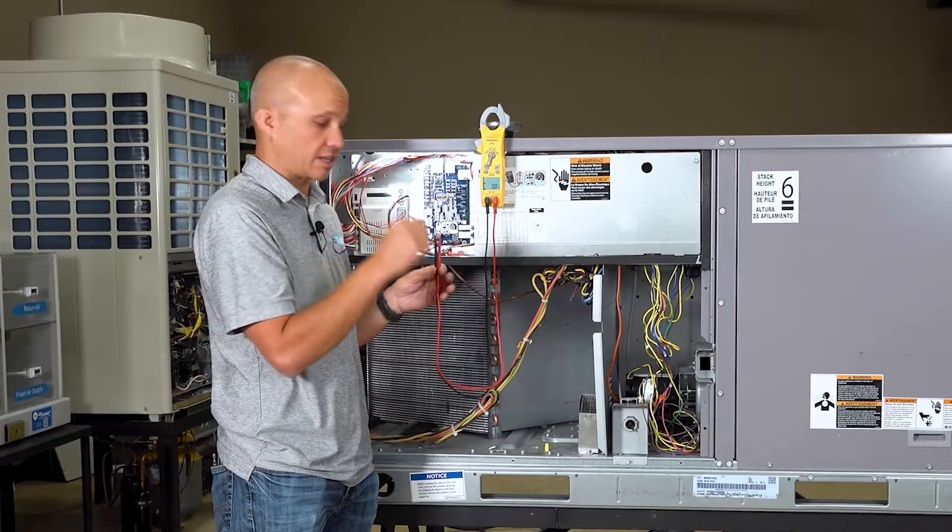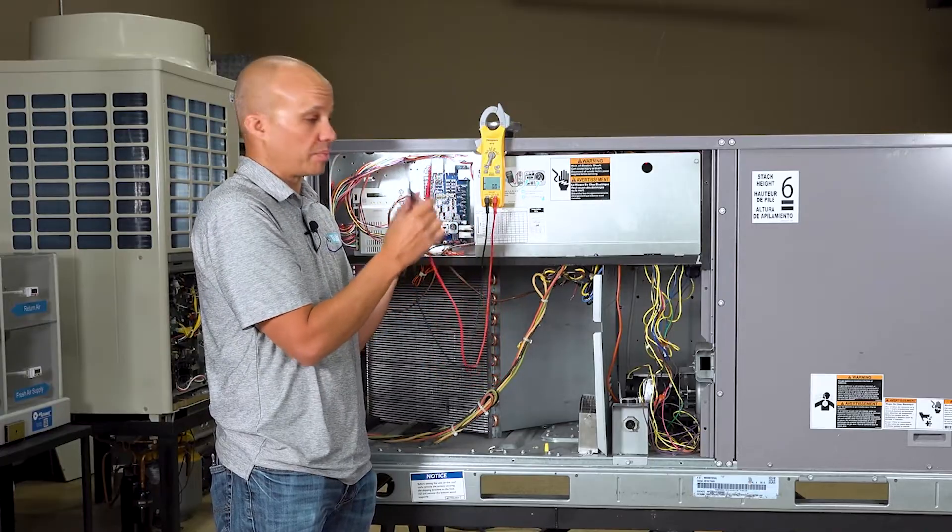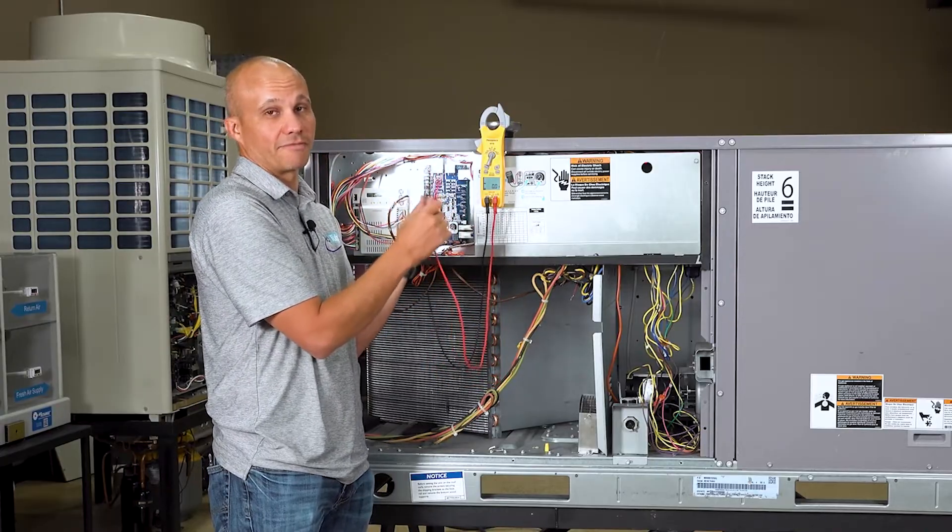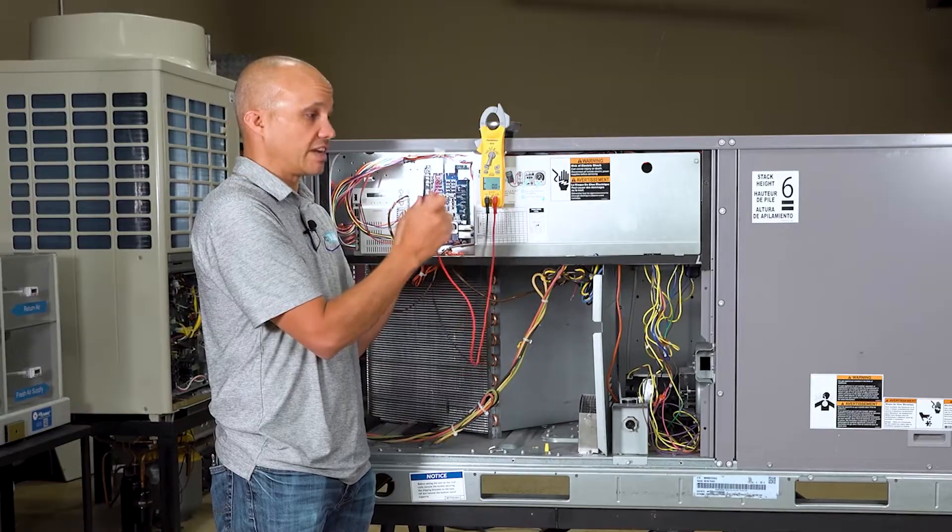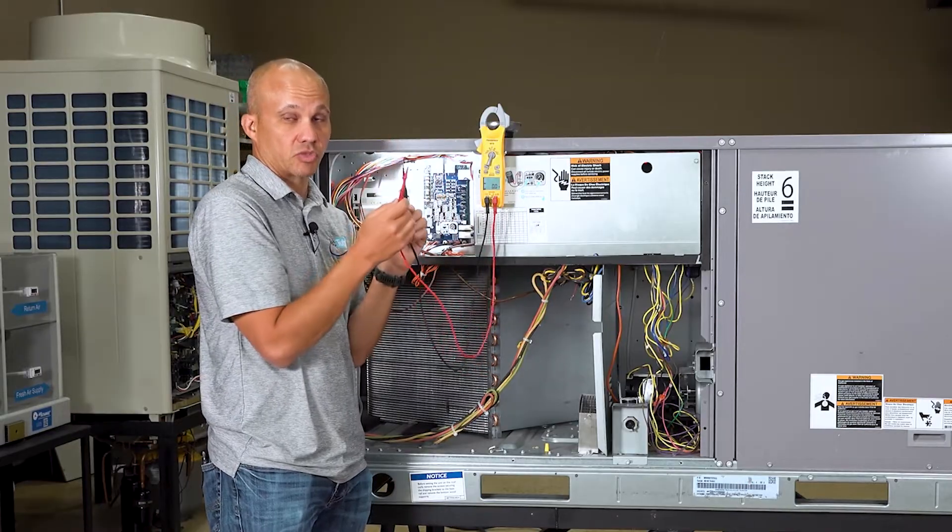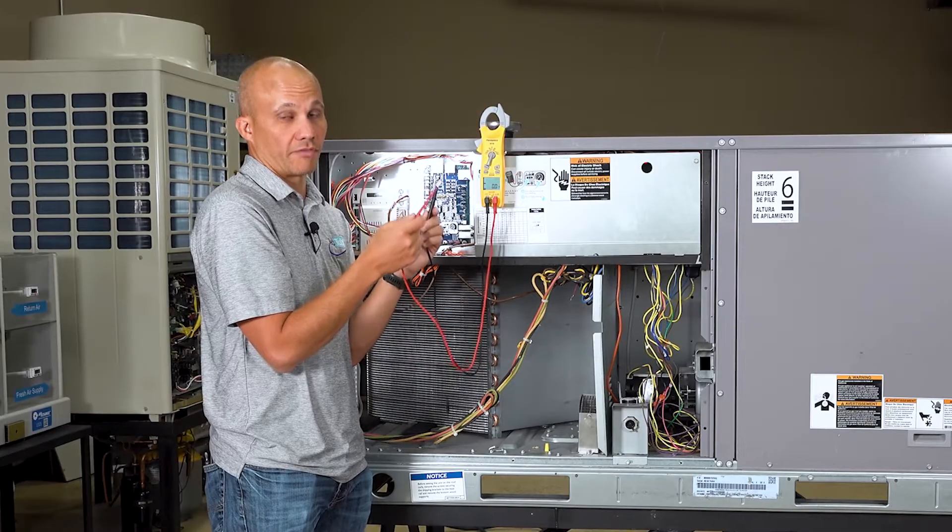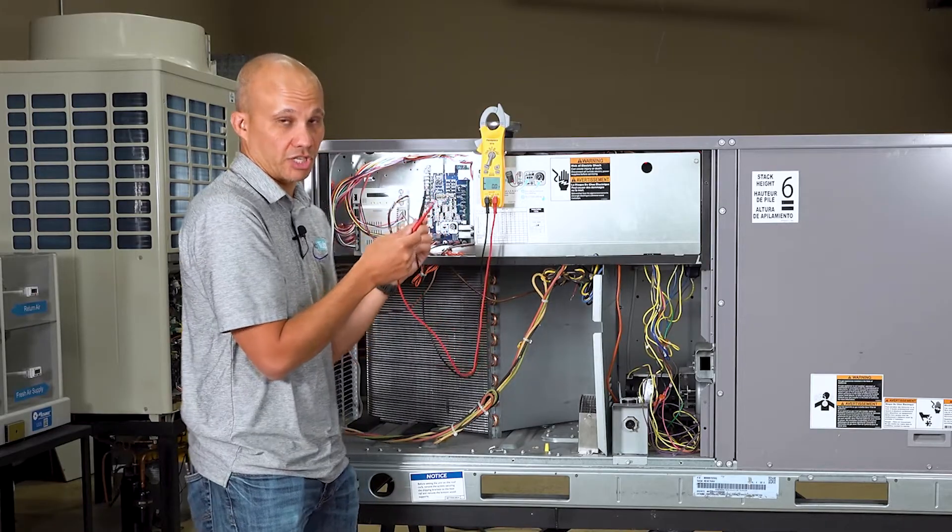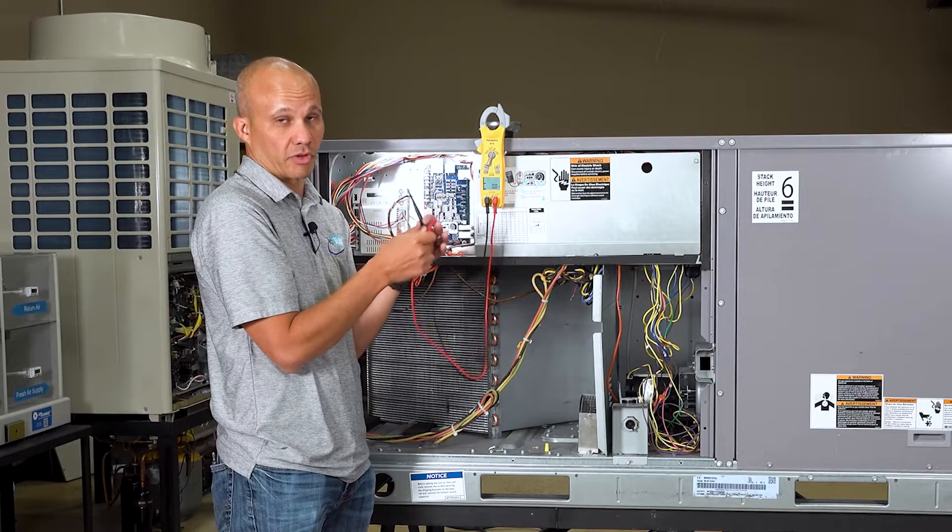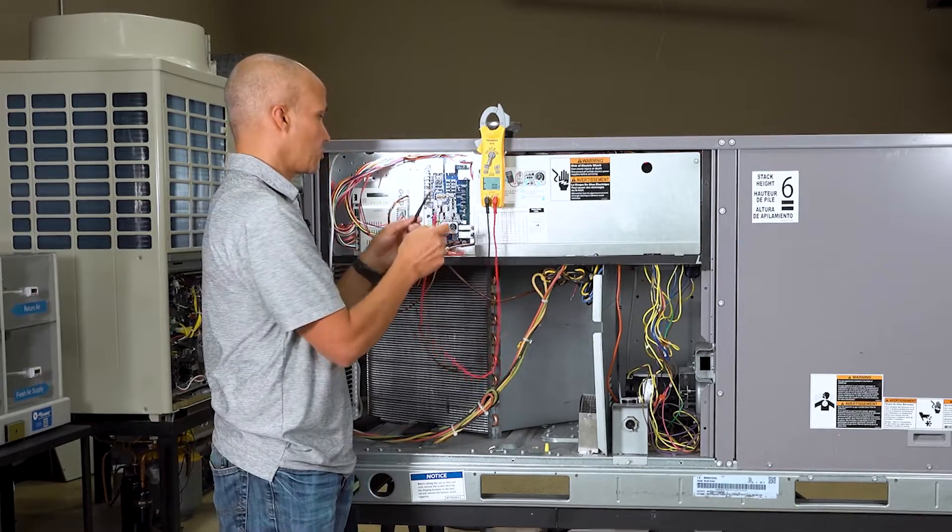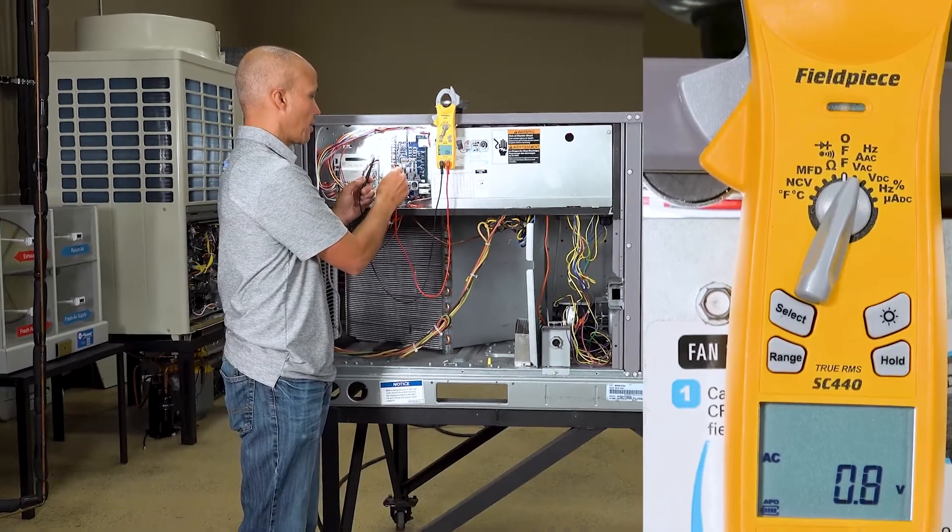When it calls for fan it closes that switch and my meter can pick that up. This meter reads differential voltage. So the difference between these two points. If that switch in the thermostat is closed it will read zero. Zero volts. So a call for fan means no voltage on R and G. No call means I'll have 24 volts. It's kind of inverted logic.